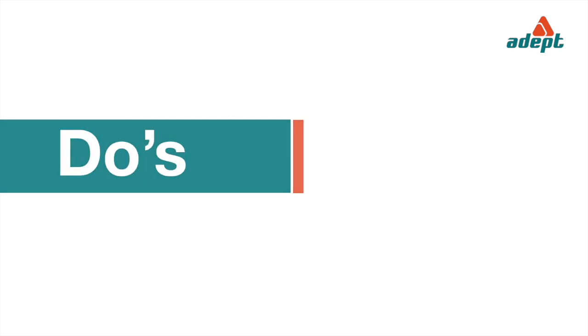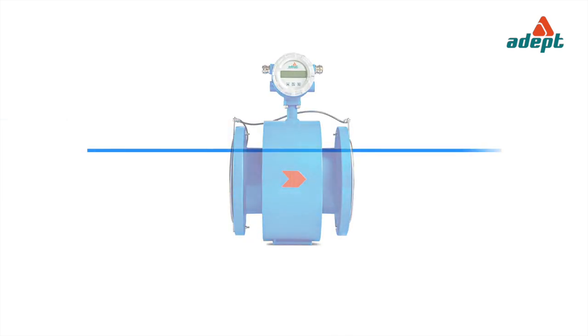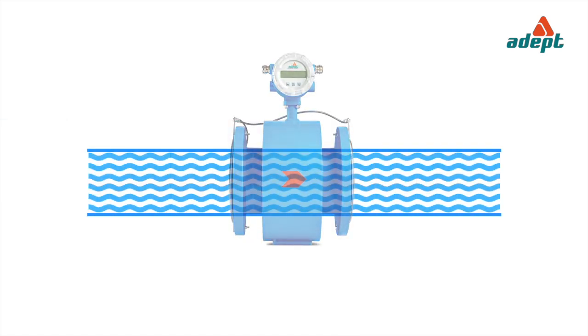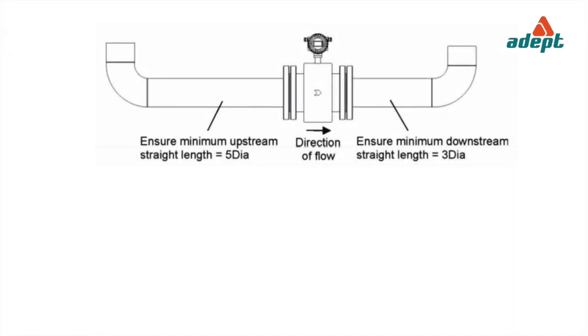Do's. Flow tube must be full of liquid to avoid erratic measurement results. Ensure straight pipe length on either end of the flow tube: 5 times pipe diameter length of piping upstream and 3 times pipe diameter downstream from the center of the flow tube.